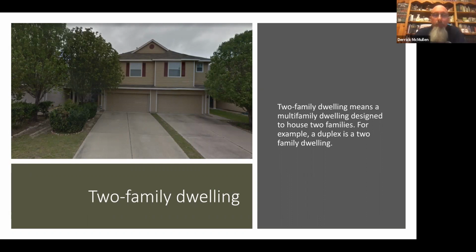I mean, there are some people out there that live with holes in their walls, but that is your fire separation. And the structure, the studs, the seal, top seal, bottom seal, that's all in between. It's normally going to be drywall on each side. It could be 2 5/8 inch type X on each side to get you 1 hour. But the engineer will determine.